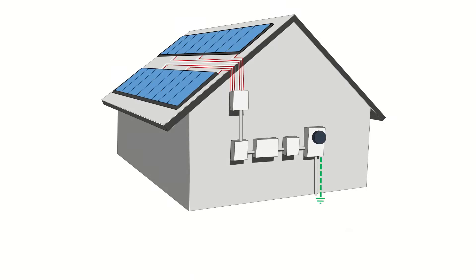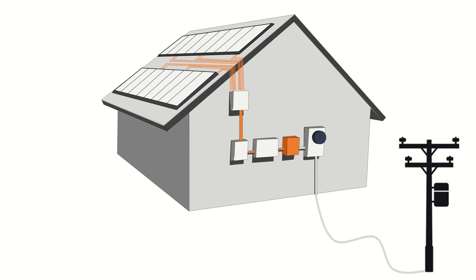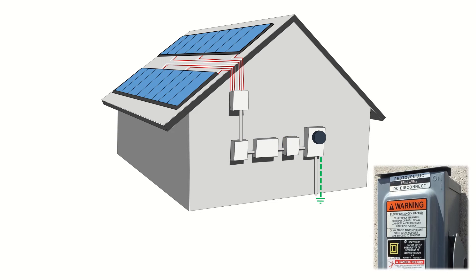Local regulations will vary, but Article 690 of the NEC details the electrical requirements for solar PV systems, including system disconnects. These disconnects are typically mounted outside at the service entrance within 10 or 15 feet, or in direct line of sight of your main billing meter. But you'll need to check with your authority having jurisdiction for specific details on placement requirements in your area. External operation allows the power to be quickly and conveniently disconnected. This switch must also be well labeled.